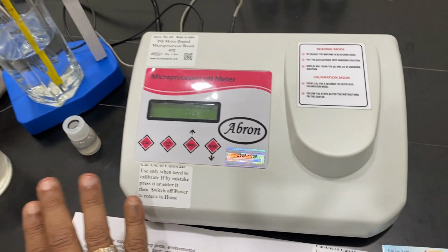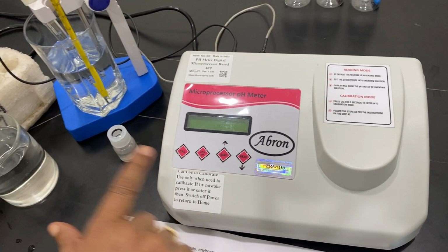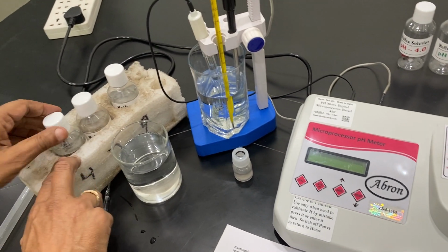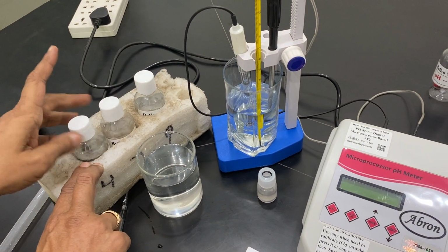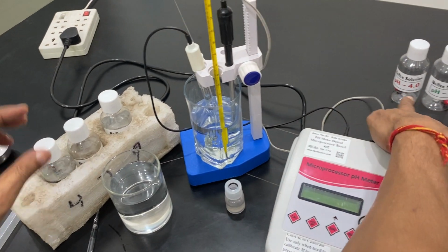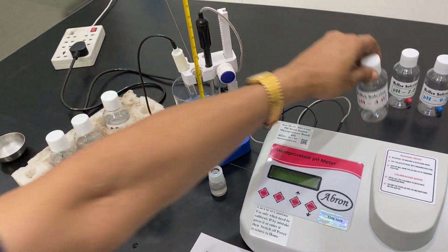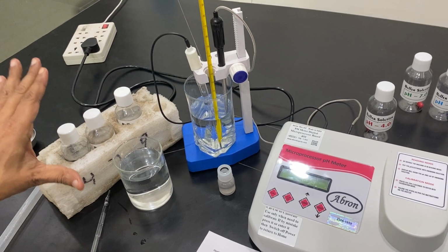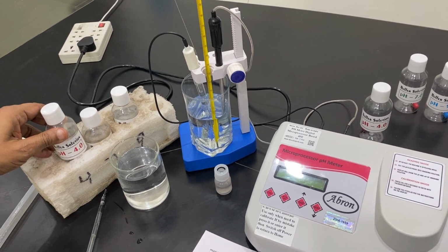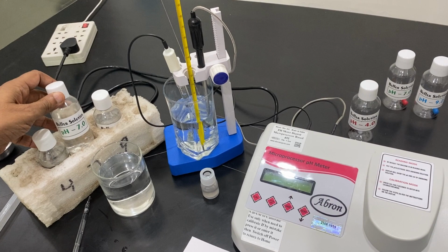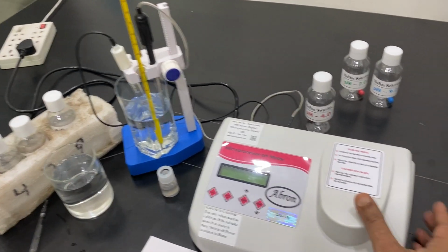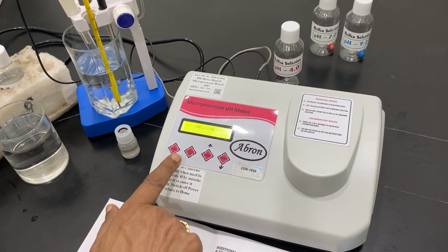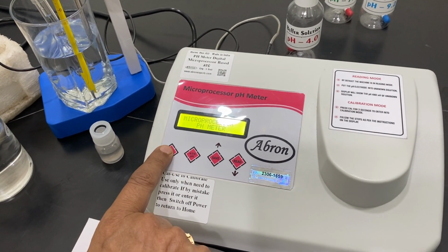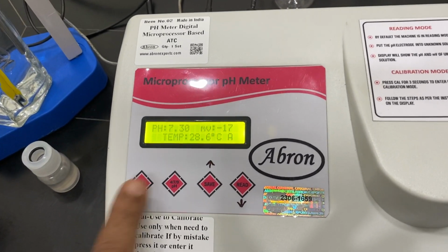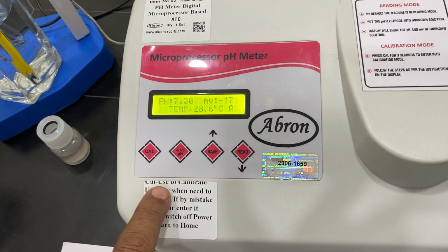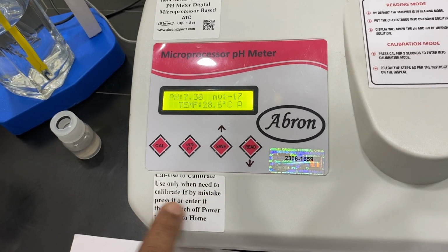The next point is, if you want to calibrate, keep the solutions ready. Make them in 100 ml of distilled water, and one capsule is provided like this. This capsule should be dissolved and then you should wait for about 2 hours. Make 3 solutions, pH 4, pH 7 and pH 9, and when you switch on, connect this and press calibration mode. Then only it goes to calibration. But be careful, cal should be used only when you need to calibrate.